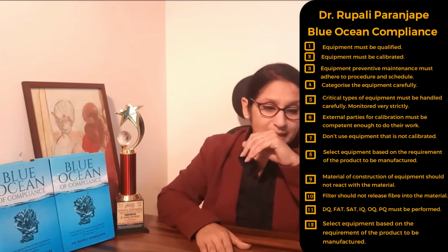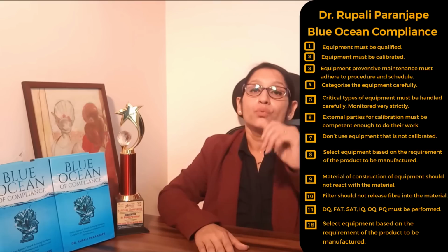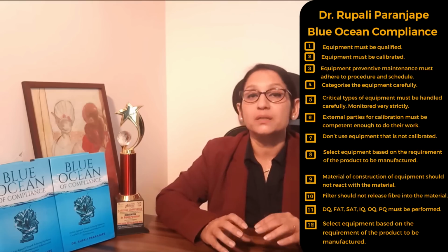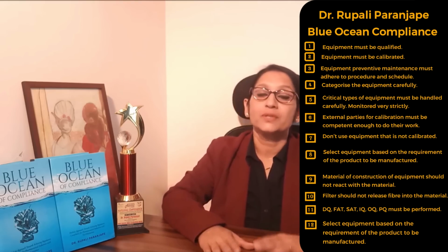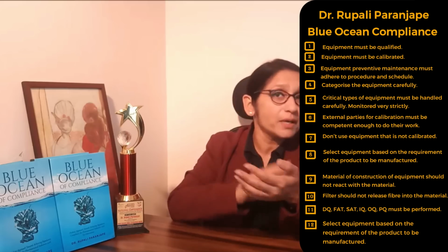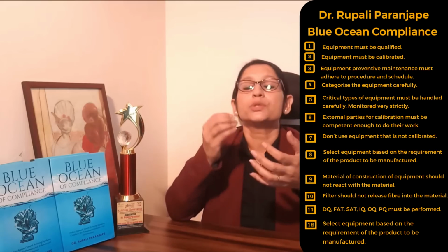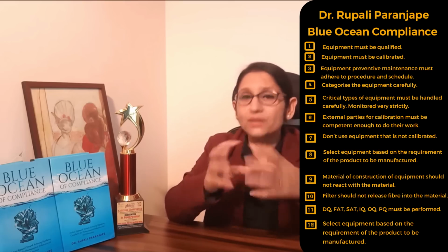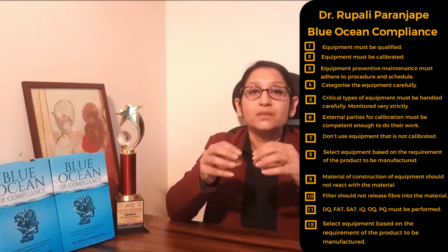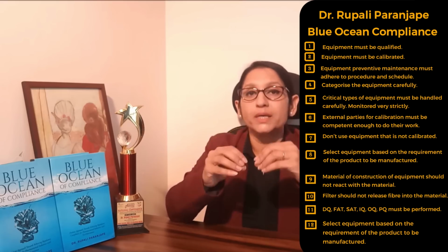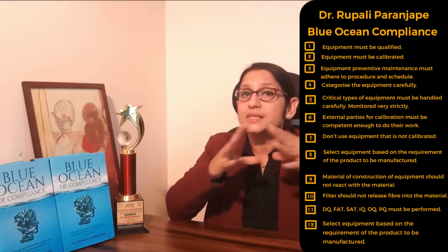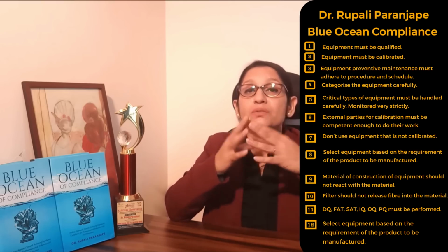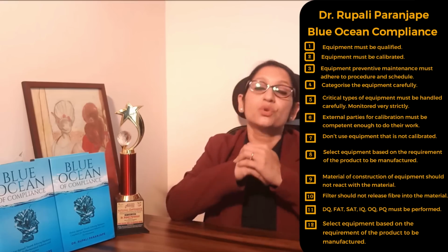Another point is the material of construction, right? Whenever you are going to manufacture any batch, the material of construction of that equipment should be such that it does not react with the product, and the equipment will not absorb the material. Otherwise there will be an impact on the safety, quality, and potency of the product. So these are the things you will have to keep in mind while selecting the equipment, about the material of construction of that equipment.